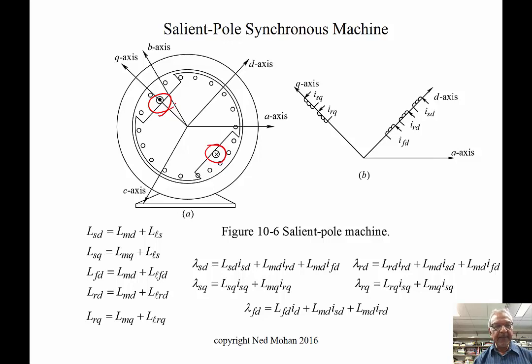The reason for this damper winding is to provide damping. When this machine is rotating at synchronous speed, where the d-axis is rotating at the speed of the rotor in steady state, there is no voltage induced in these damper bars. Therefore, there's no role for the damper winding.